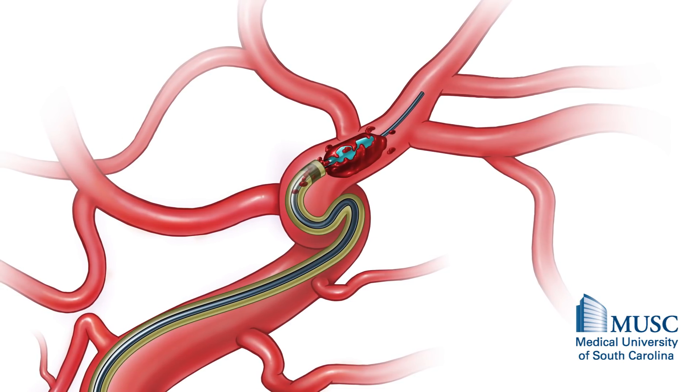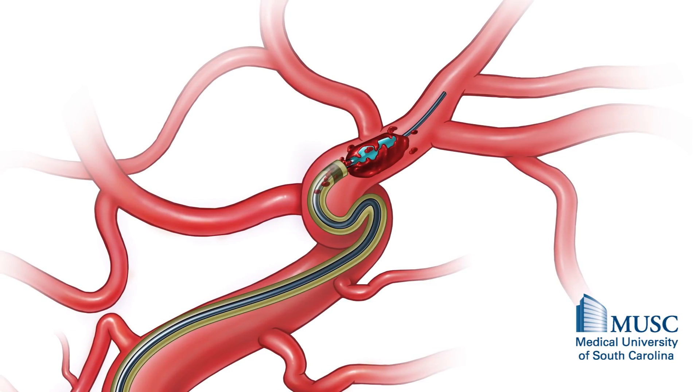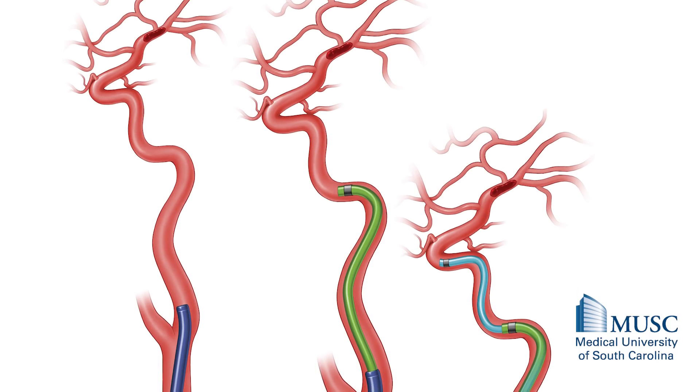Before that, the company sold the catheters, but they had these little wires with stoppers on the end that they used to break up the clot and then clear the end of the catheter. But what we found was that basically just fragmented the clot and sent it more downstream, and we'd have to work our way through the vascular tree to open one size vessel and then go the next smaller and next smaller. But with the aspiration alone, without breaking up the clot, we're able to pull the entire clot out the majority of the time. So it gave us the idea that if we can just take a catheter, drive it to the clot, turn on suction and pull the clot out, or have it get sucked through the catheter, that would be much simpler and really a home-run way to go.